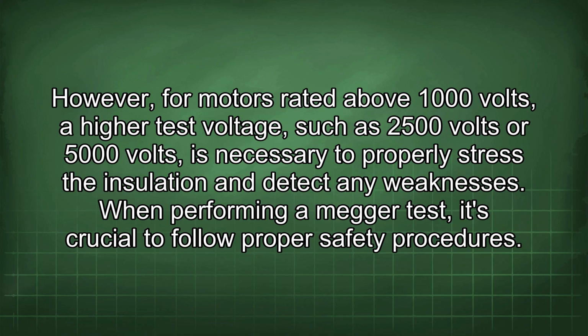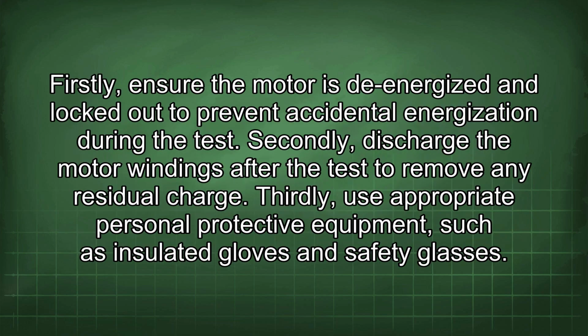When performing a Megger test, it's crucial to follow proper safety procedures. Firstly, ensure the motor is de-energized and locked out to prevent accidental energization during the test. Secondly, discharge the motor windings after the test to remove any residual charge. Thirdly, use appropriate personal protective equipment, such as insulated gloves and safety glasses.